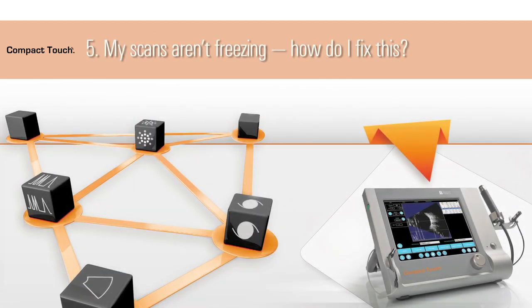5. My scans aren't freezing. How do I fix this? If this is happening infrequently, it's probably not a technical issue and has more to do with technique or probe positioning. Ensure that the technique settings are correct (contact versus immersion) and gain is normal. If this happens with all patients, it is more likely a technical issue. In this case, please contact a Quantel technician.